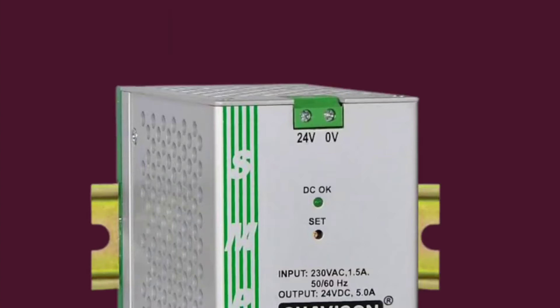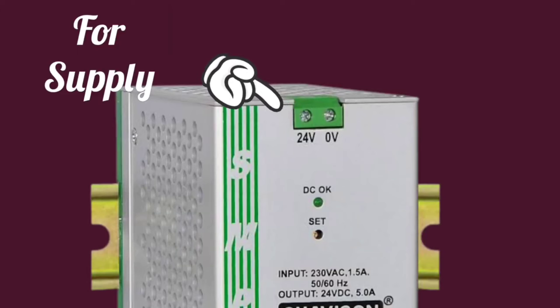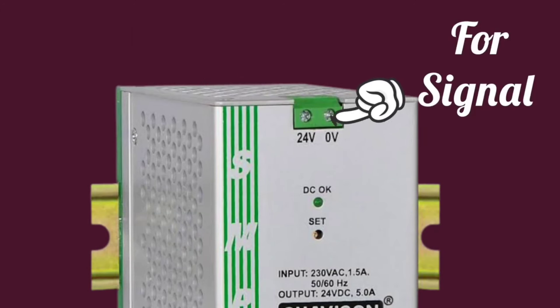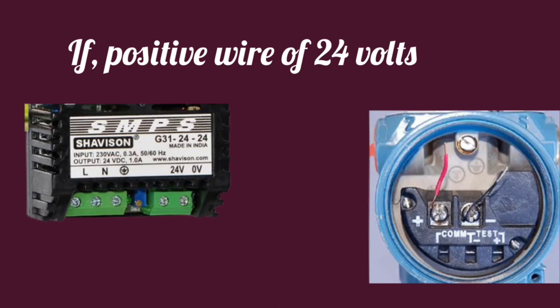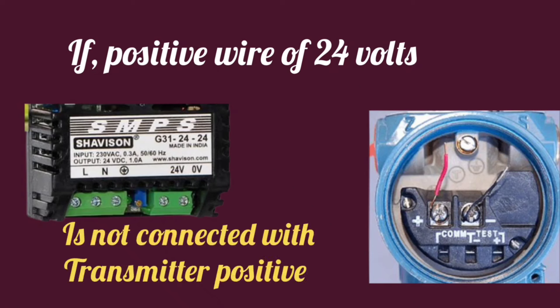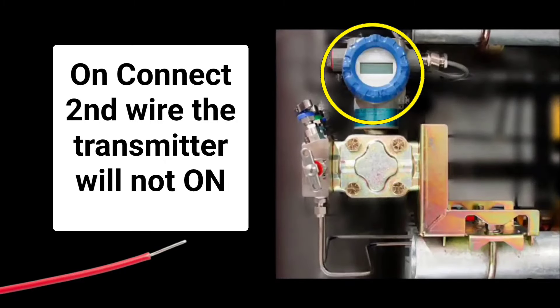We use the positive wire of 24V for supply, meaning for transmitter supply, and the other wire is used for signal. If we do not connect the positive wire of 24V supply, or the one on which 24V is written, to the positive terminal of the transmitter, if we connect the second wire to the positive of the transmitter, then the transmitter is not on.